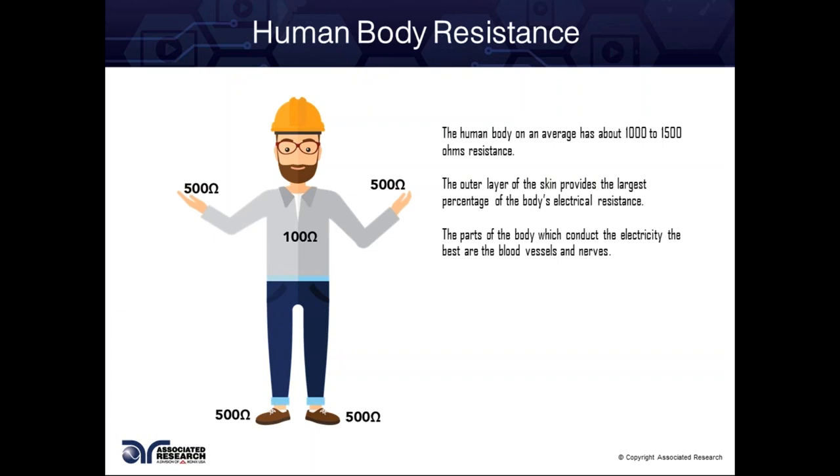Current has a few different paths to flow through a person. It can enter the arm and go down through the leg if referenced to earth. Going from one arm to the other arm is considered the most dangerous path because now you're passing current through the chest cavity where the heart is — this is where fibrillation can occur. That current alters the pattern of your heartbeat. This is why it's important to have a defibrillator around all your Hypot test stations.